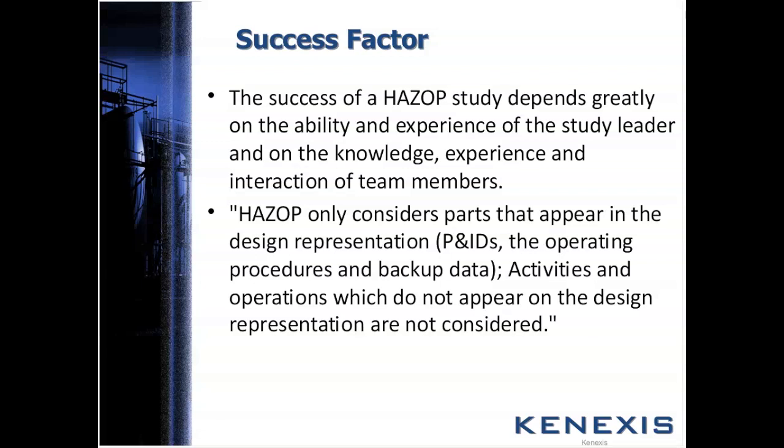So that's pretty much it for the PHA overviews, and you can see that safety instrumented functions accrue during the entire life cycle of the plant, and will more likely accrue when you get into the HAZOP, fault trees, and some of the more sophisticated techniques, because they can delineate the independent protection layers that are available to circumvent a problem, and then accurately determine whether the risk is acceptable. So our objective is to meet acceptable risk with the safety instrumented functions.